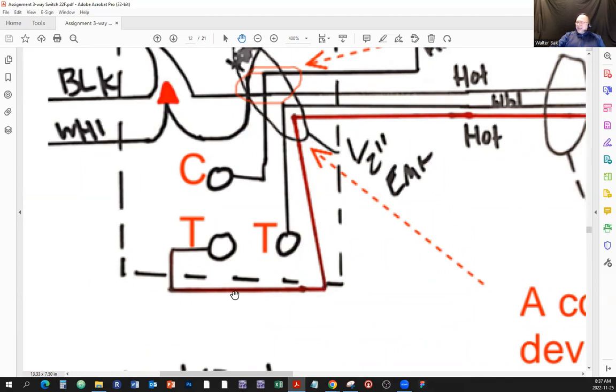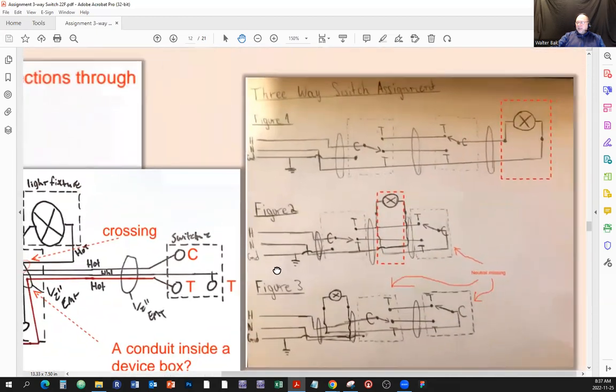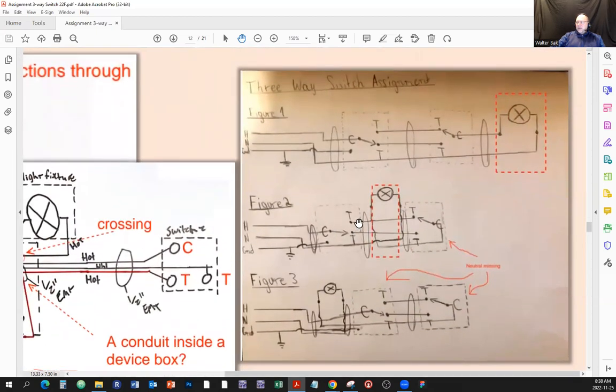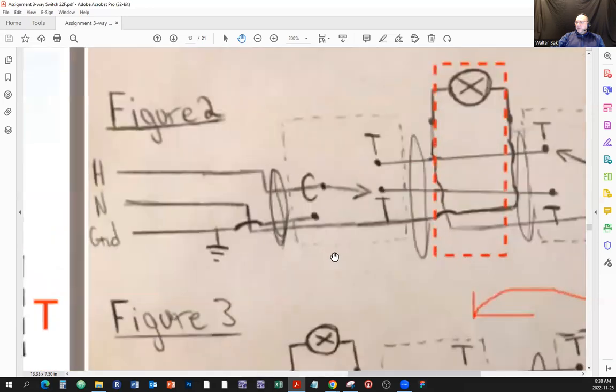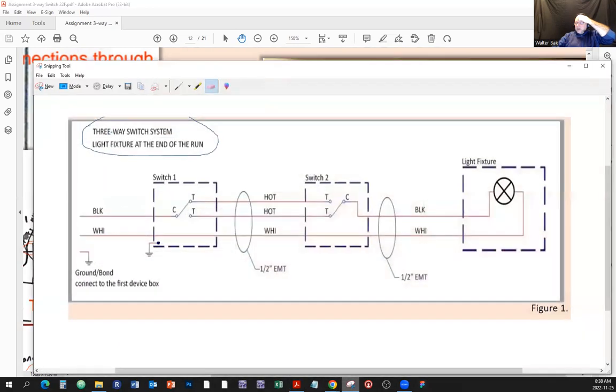Here a line goes from the traveler, outside the box, comes back into the box, going diagonally — just why? Go straight. Don't come out of the box and go back in. Make a decision which direction you want to go. Overall this is a mess, unacceptable. Would you pay for something like this if somebody did it for you? Present your work properly — do it by hand with a ruler, it'll take a couple more minutes but it will sink into your brain.